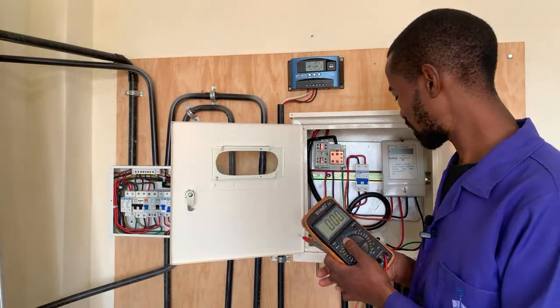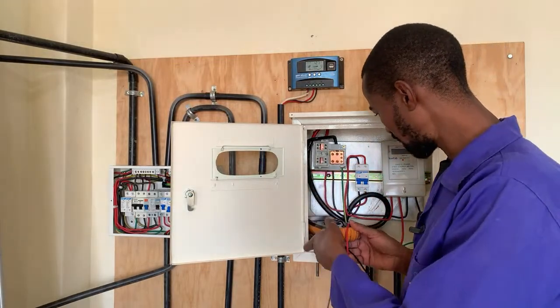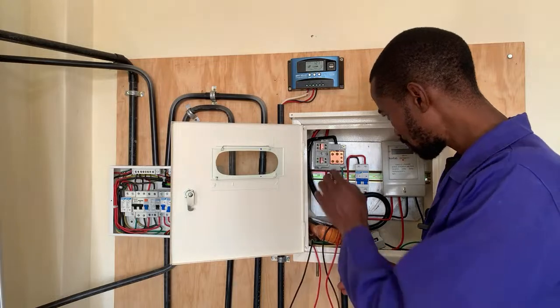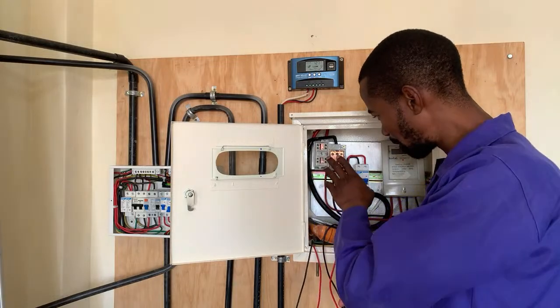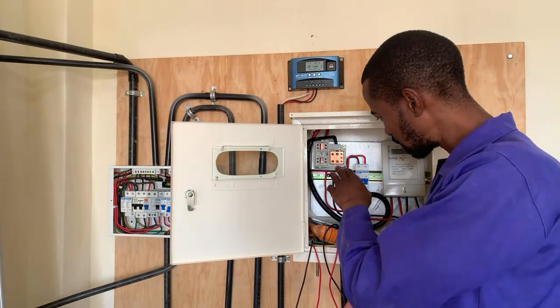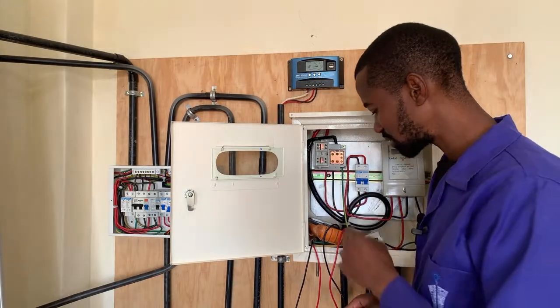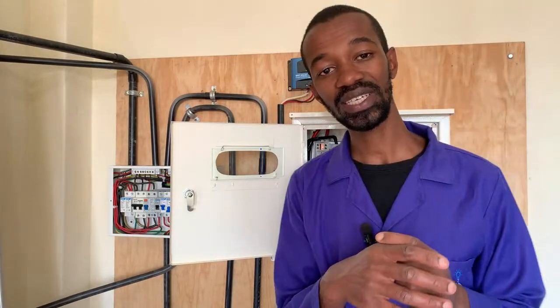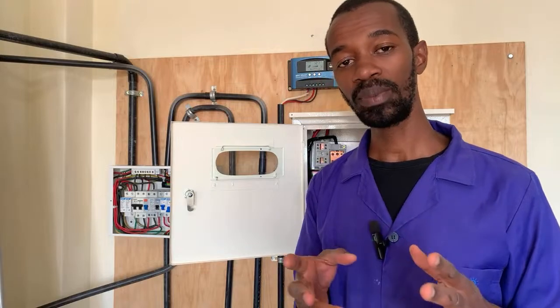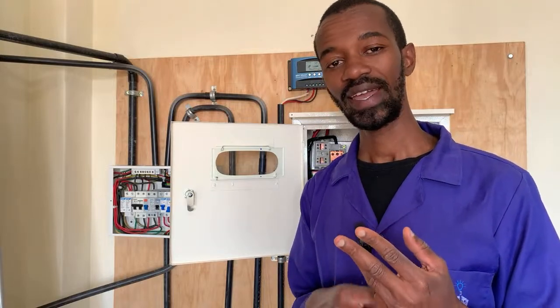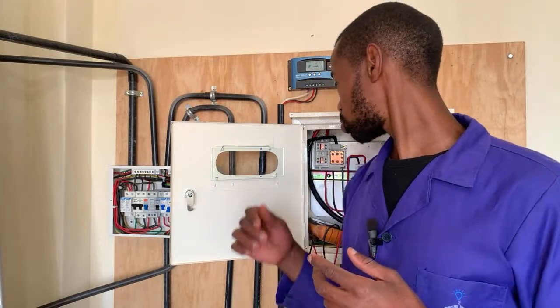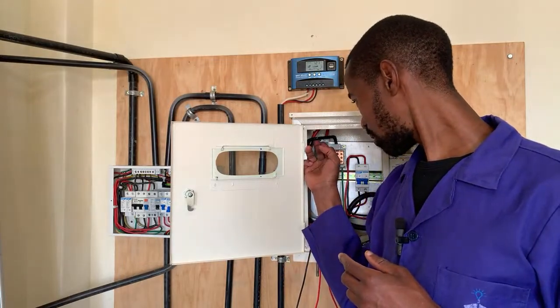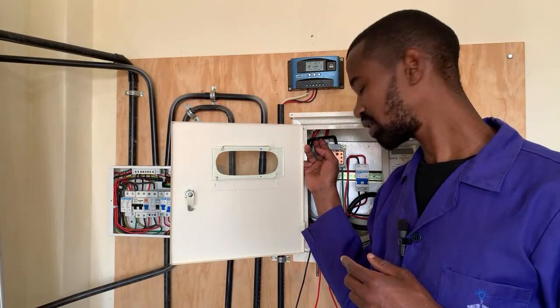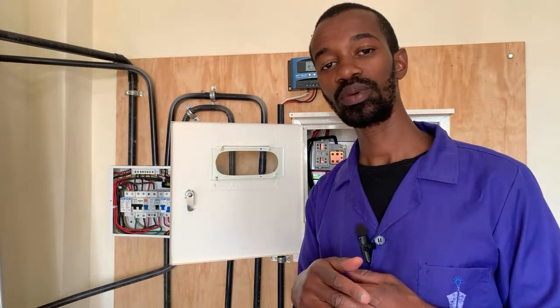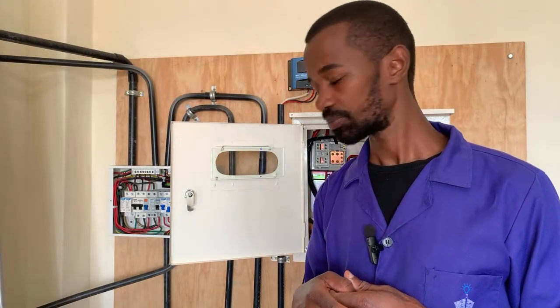I will try to find out where the problem could be, and it would mean the drop cable feeding power to these double cutouts has an issue, or the cutout itself has an issue. Probably there is a loose connection, and I'll need to disconnect this cable here and see what could be the problem.